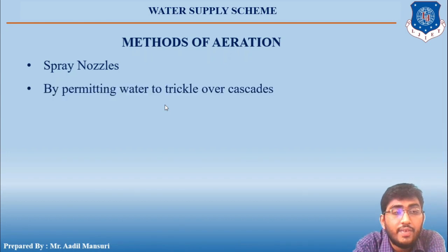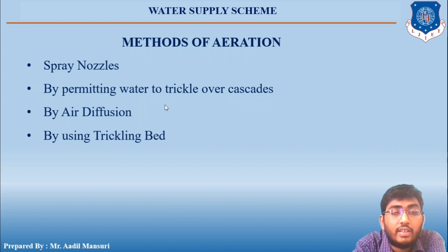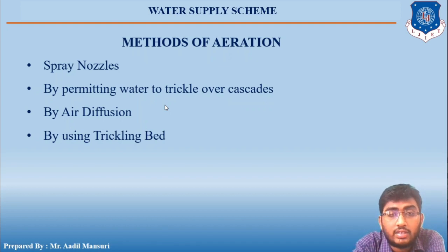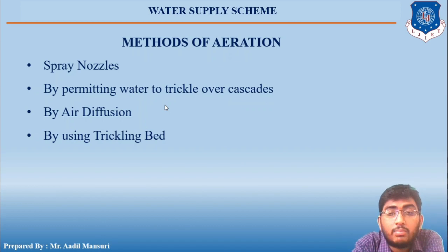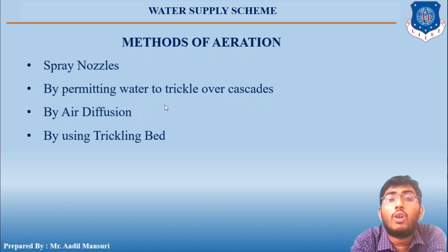The different methods of aeration include: spray nozzles, permitting water to trickle over a cascade, air diffusion, and using trickling beds. In all these methods, contact between air and water is made either by formation of small drops or thin layers, or by means of formation of small air bubbles.